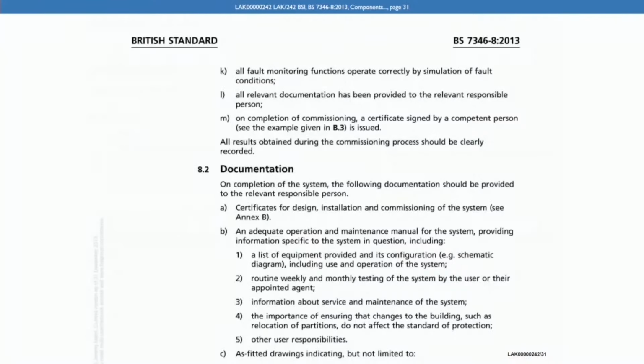I see. But does that answer mean that there were some results that you took during the commissioning process that didn't then make its way into recorded documentation? Not as far as I'm aware. All the results that I recorded were all recorded and issued. Yes. Below that, under documentation, it then says, on completion of the system, the following documentation should be provided to the relevant responsible person. And A is the certificates for design, installation and commissioning.